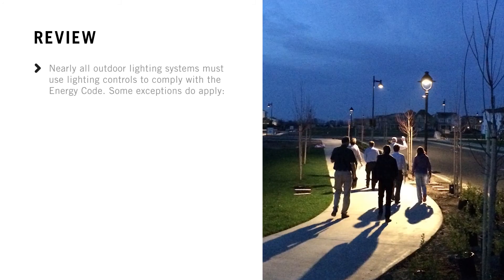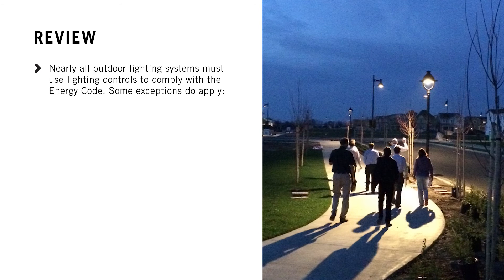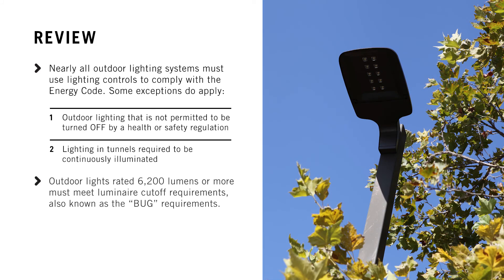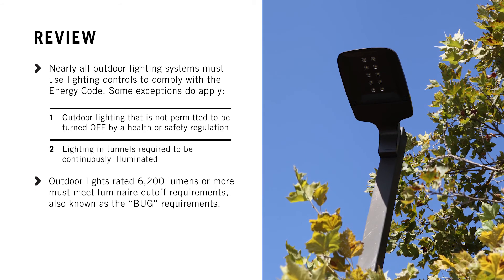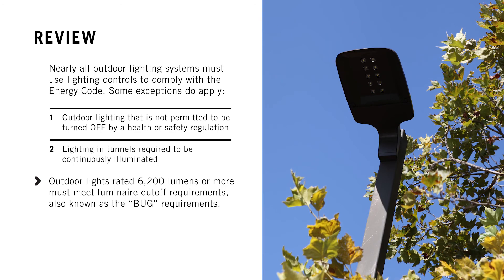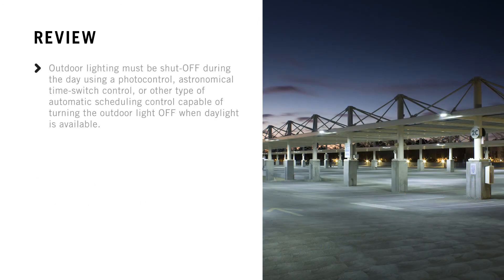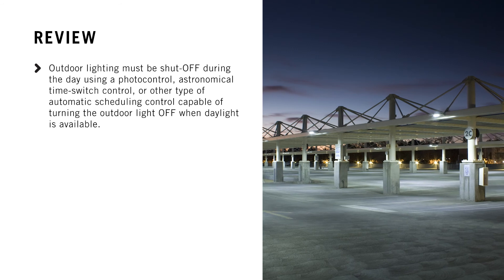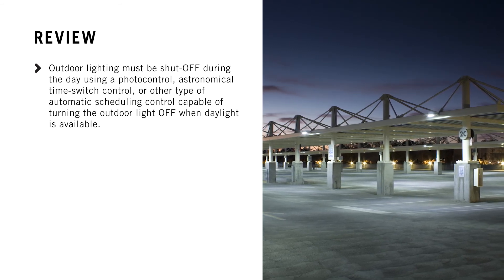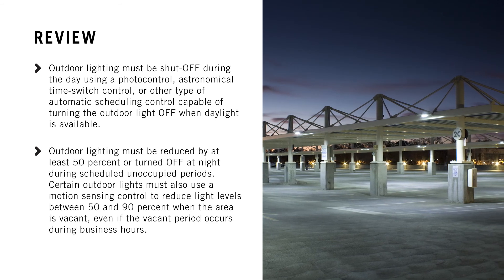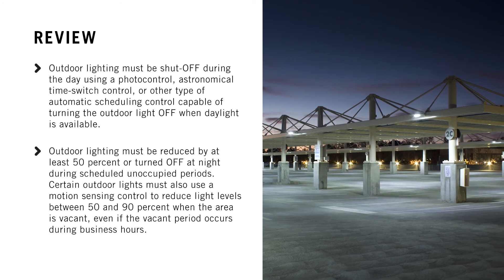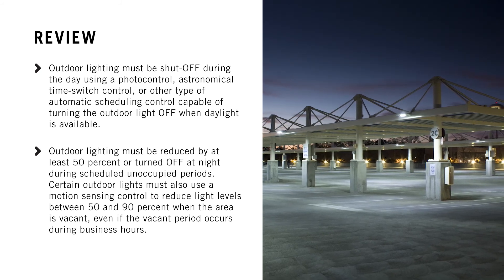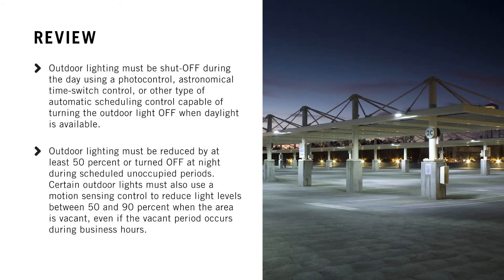Let's review what we've learned. Nearly all outdoor lighting systems must include lighting controls to comply with the Energy Code; some exceptions do apply. Outdoor lights rated 6200 lumens or more must meet luminaire cutoff requirements, also known as the BUG requirements. Outdoor lighting must be shut off during the day using a photo control, astronomical time switch control, or other type of automatic scheduling control capable of turning the outdoor lighting off when daylight is available. Outdoor lighting must be reduced by at least 50 percent or turned off at night during scheduled unoccupied periods. Certain outdoor lights must also use a motion sensing control to reduce light levels between 50 and 90 percent when the area is vacant, even if the vacant period occurs during business hours.